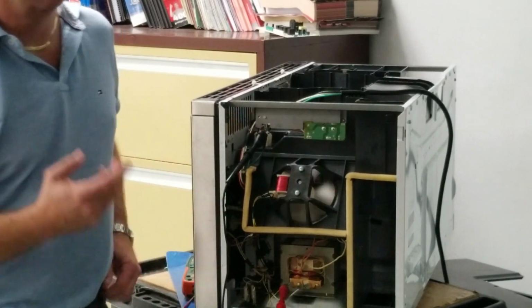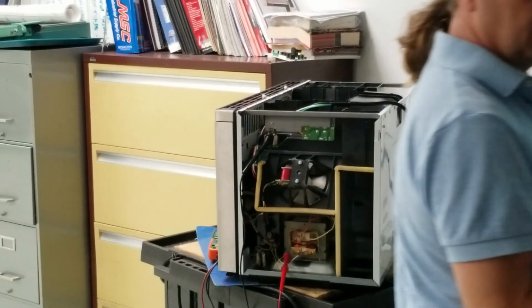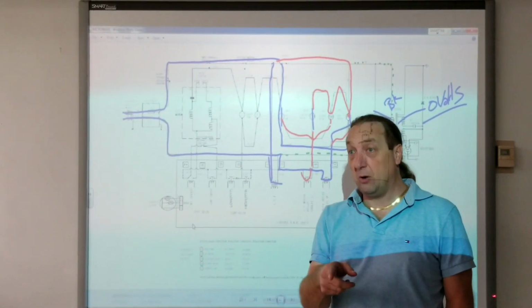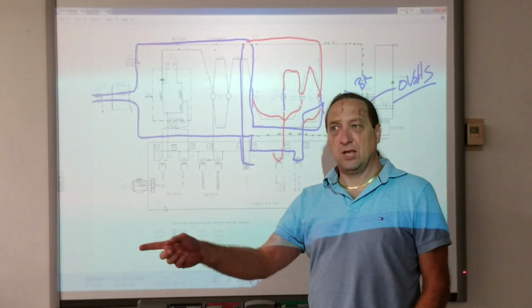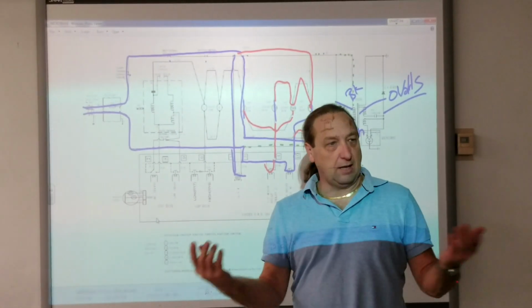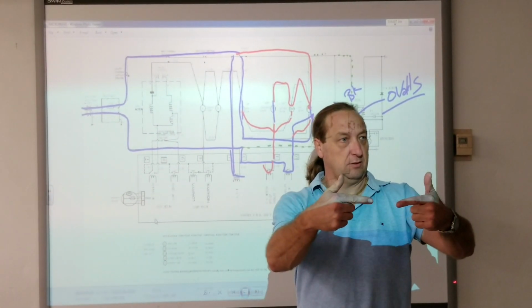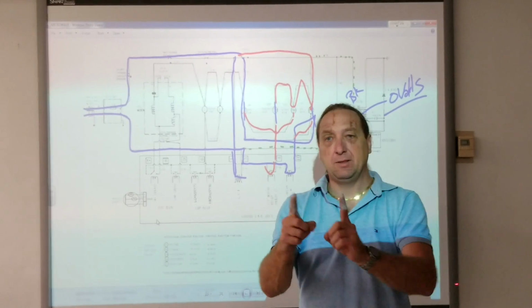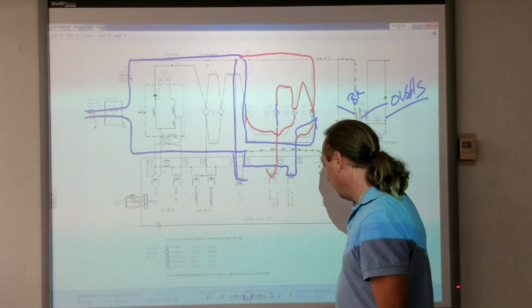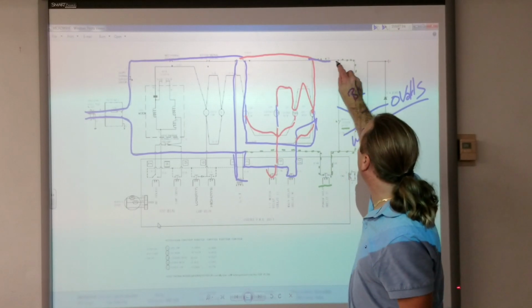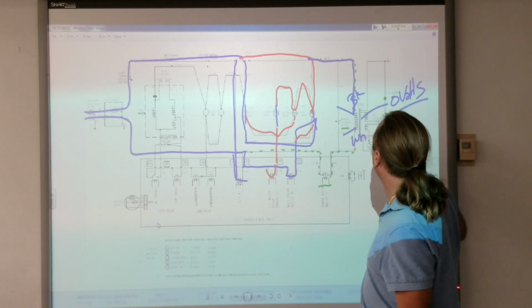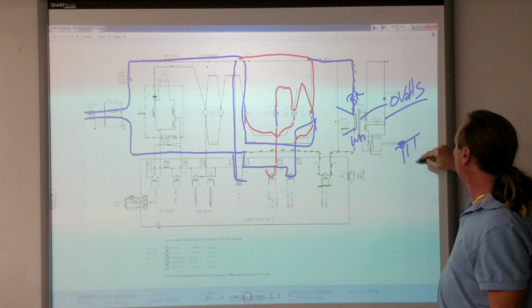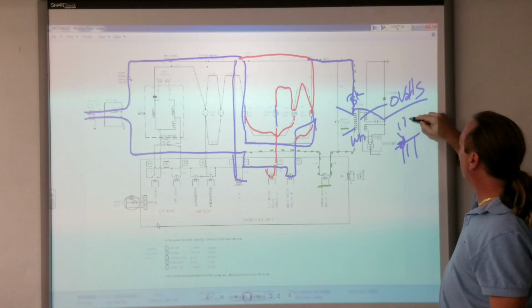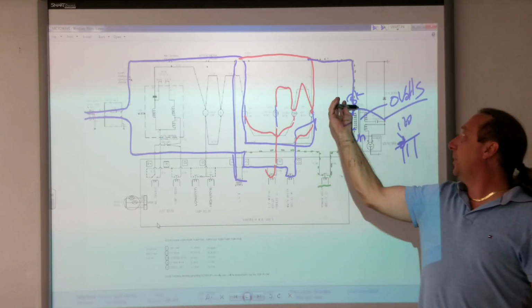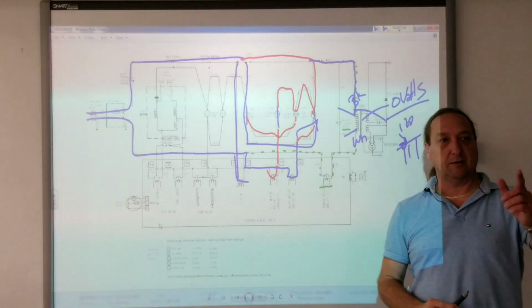So, what does that mean? That means line one is good. That means power's coming into the transformer. I just said a minute ago, I don't have power. Well, it takes two lines to make voltage. But the test I made is telling me that the black line coming into here is good. To ground is 120 volts. So I know back here is good. Yes, you got a question?